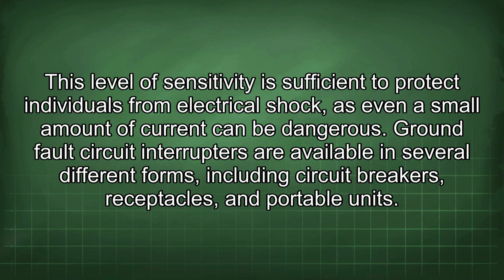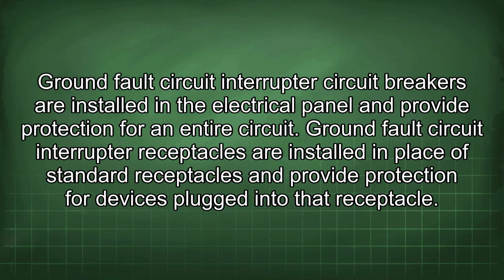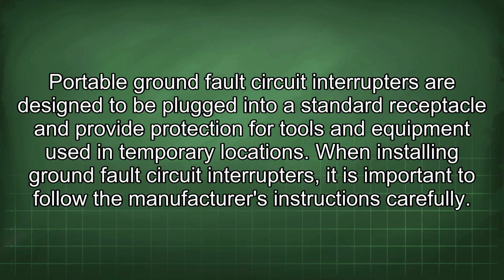Ground fault circuit interrupters are available in several different forms, including circuit breakers, receptacles, and portable units. Ground fault circuit interrupter circuit breakers are installed in the electrical panel and provide protection for an entire circuit. Ground fault circuit interrupter receptacles are installed in place of standard receptacles and provide protection for devices plugged into that receptacle. Portable ground fault circuit interrupters are designed to be plugged into a standard receptacle and provide protection for tools and equipment used in temporary locations.